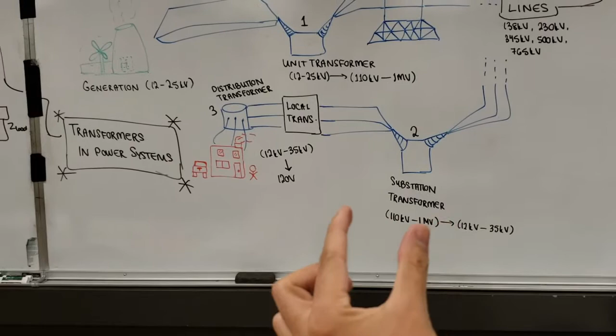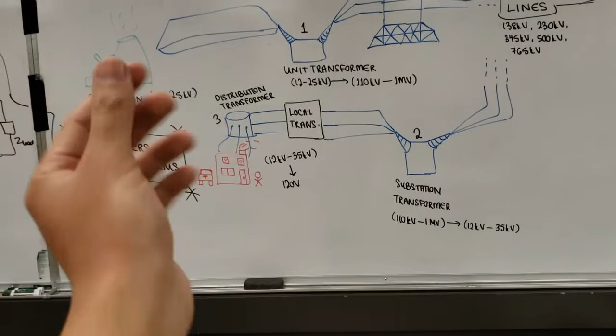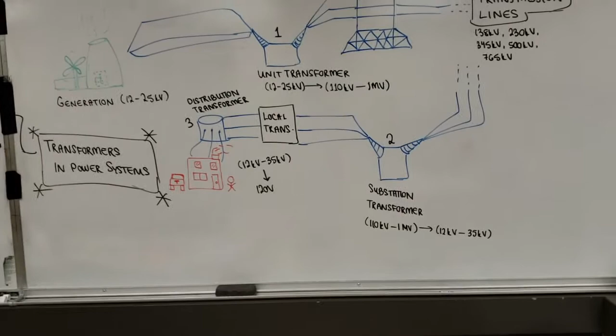And then, coming down after a certain amount of distance, you have your substation. This is a lot closer to you in terms of distance. What it does is bring that high voltage power line back down to the voltages seen originally at the generation, 12 to 35 kilovolts.